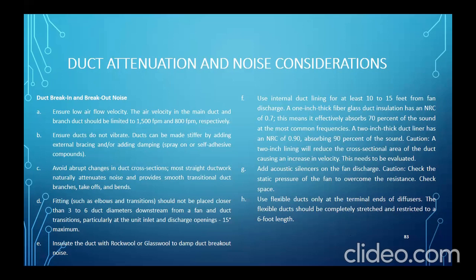C. Avoid abrupt changes in duct cross sections. Most straight ductwork naturally attenuates noise and provides smooth transitional duct runs, takeoffs, and bends. So, ibig sabihin ng avoid, minimize mo. Okay? So, hindi maiwasan, so lalagyan mo ng liner. Fittings such as elbows and transitions should not be placed closer than 3 to 6 duct diameters downstream from a fan. Duct transition, particularly at the unit inlet and discharge opening, 15 degrees maximum. Ito yan, di ba, yung mga transition mo 15 degrees both sides, hindi bigla, dahil nga yung noise.